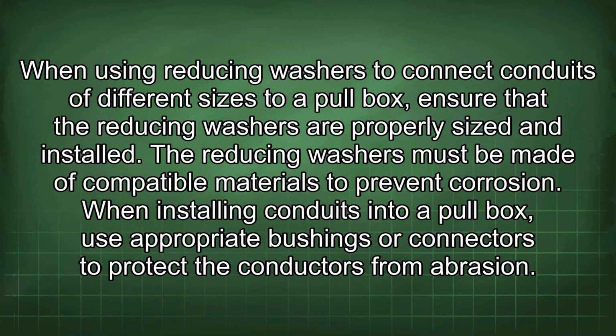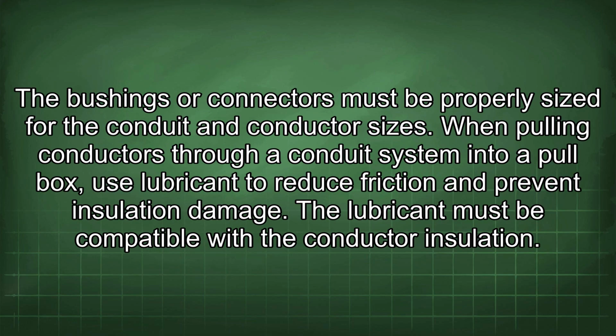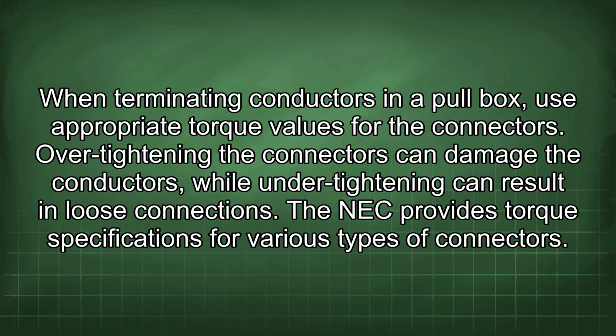When installing conduits into a pull box, use appropriate bushings or connectors to protect the conductors from abrasion. The bushings or connectors must be properly sized for the conduit and conductor sizes. When pulling conductors through a conduit system into a pull box, use lubricant to reduce friction and prevent insulation damage. The lubricant must be compatible with the conductor insulation. When terminating conductors in a pull box, use appropriate torque values for the connectors. Over-tightening the connectors can damage the conductors, while under-tightening can result in loose connections. The NEC provides torque specifications for various types of connectors.